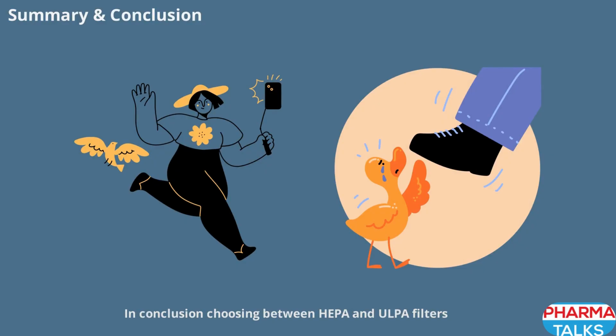Conclusion: choosing between HEPA and ULPA filters depends on your cleanroom's specific needs, regulatory requirements, and risk assessment. HEPA filters are the standard for most pharmaceutical applications, offering a balance of efficiency, cost, and compliance. ULPA filters are reserved for ultra-critical environments where the highest level of cleanliness is required. Always ensure proper installation, validation, and ongoing monitoring to maintain cleanroom integrity and regulatory compliance.